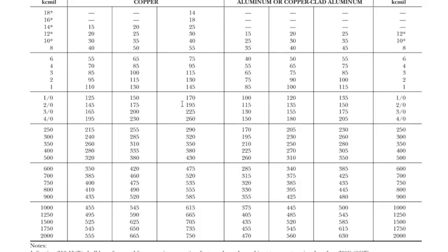Now look at how far we've come from 150. With 150, I probably would have selected the 170 wire, maybe the 195. And I would have done the math for those two and gone, nope, and kept going. And would I have started with 400 kcmil? No way.